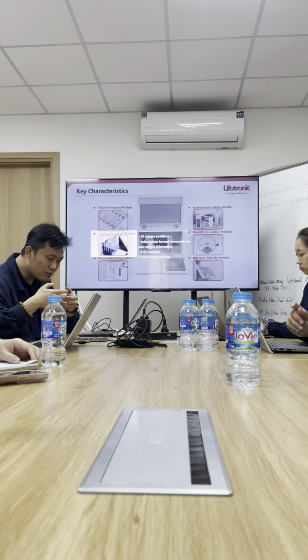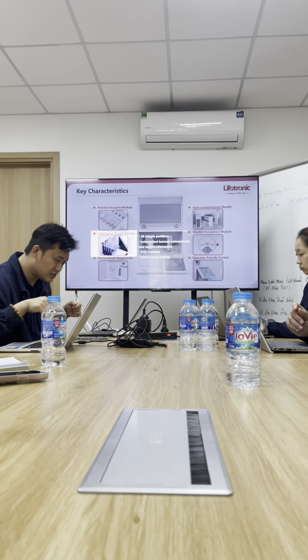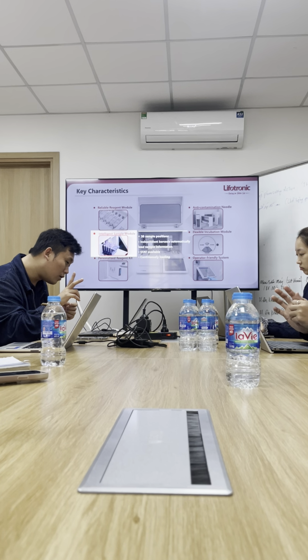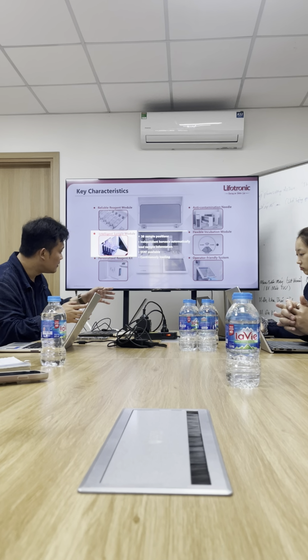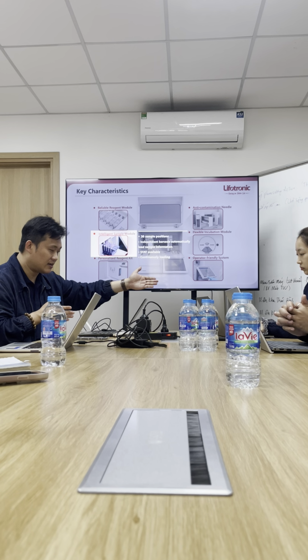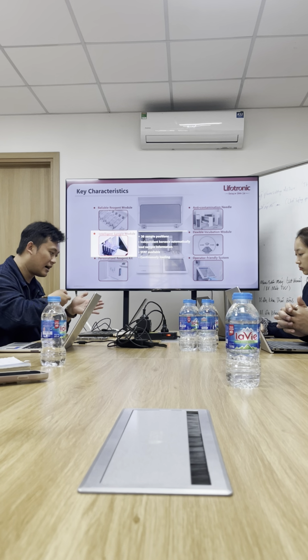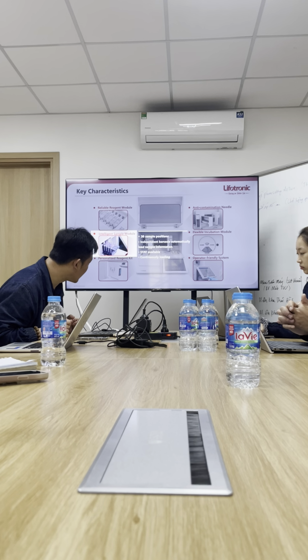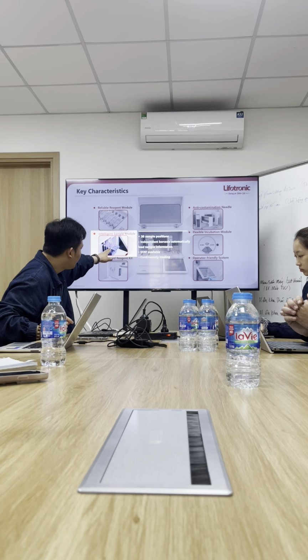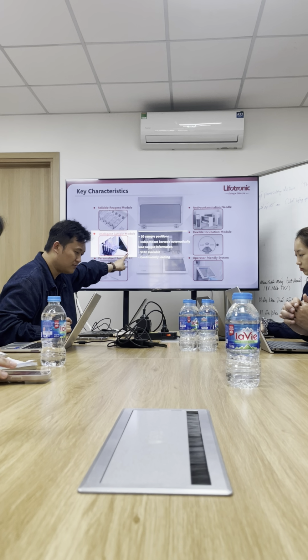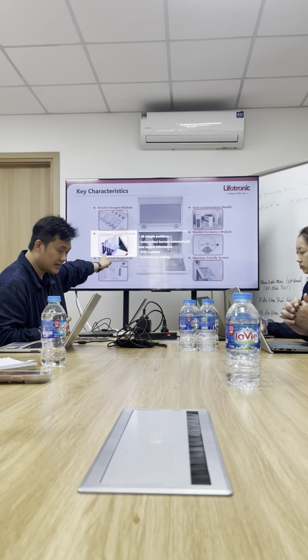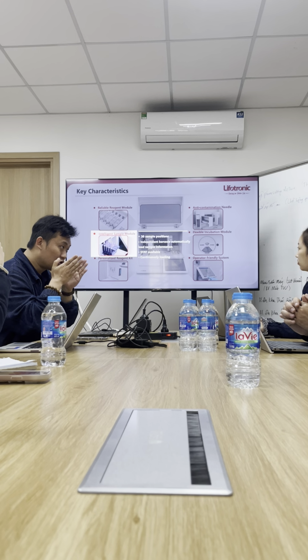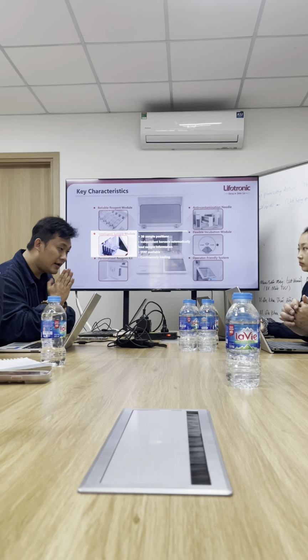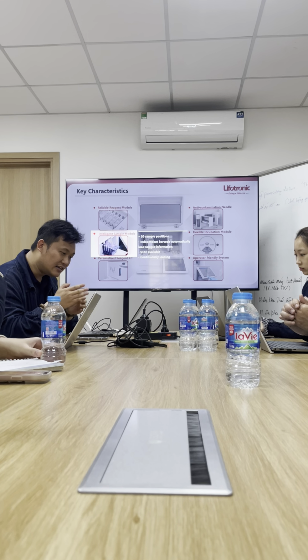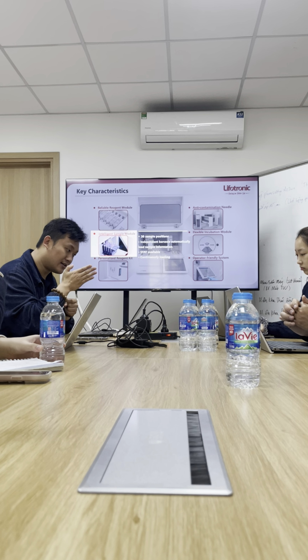Even when you come to a new rack of samples, you can insert it into the third rack, or it's fully racked. The first rack is already summed up, complete sampling. You can take it out for the new samplings as well. And each sampling position can be set as a stat sample. The stat sample means there's no need for waiting. It can test right now.